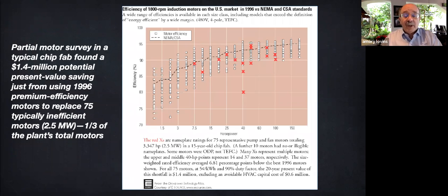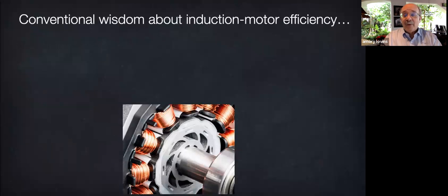Many factory managers inattentively run every motor till it breaks, it fails, even if it is grossly inefficient. They have other stuff to worry about. Well, conventional analyses like IEA's typically assume a package of just 2 drive system improvements: switching to more efficient, but often far from most efficient, motors when replacement is needed or scheduled, but not sooner, and adding ASDs, adjustable speed drives, where suitable, which it usually is.